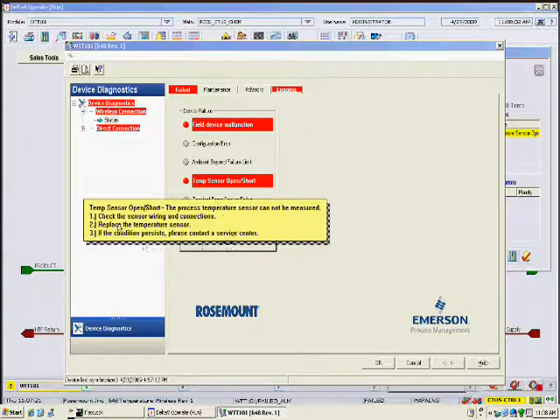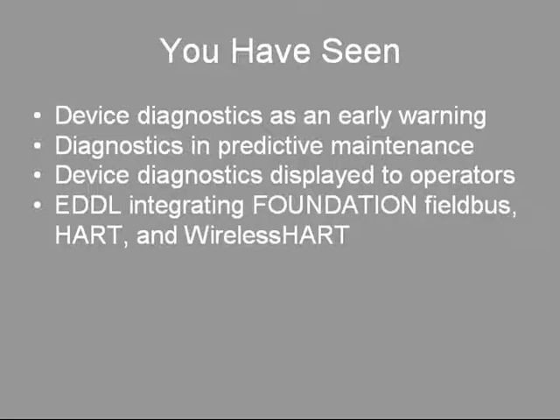The operator clicks on the help button and then on the failure indication. Manufacturer's help is displayed. If diagnostics is not integrated into the operator consoles where operators can see it and use it to act before the process is affected, chances are that diagnostics will not become a natural part of daily work practices. Diagnostics only displayed on a maintenance station that is not continuously manned will not be seen in time to make a difference. The device diagnostics and device management system may fall into disuse.